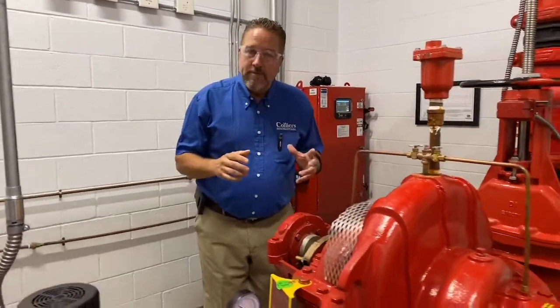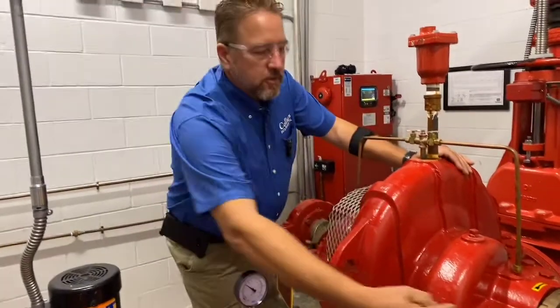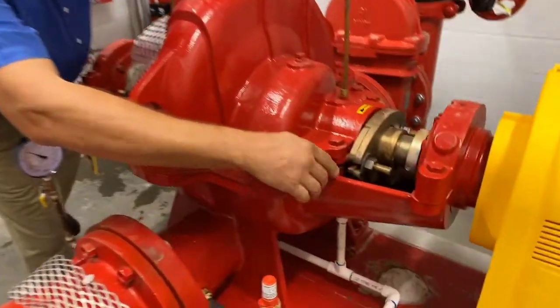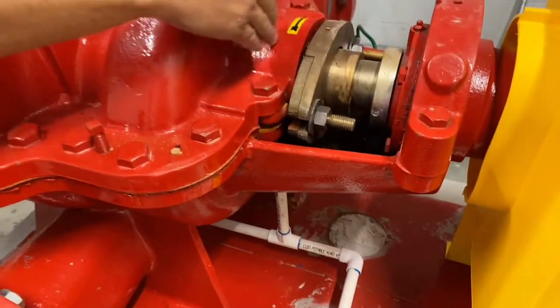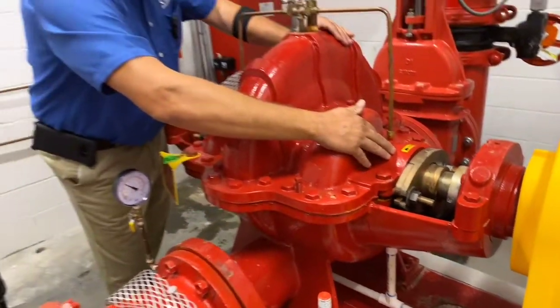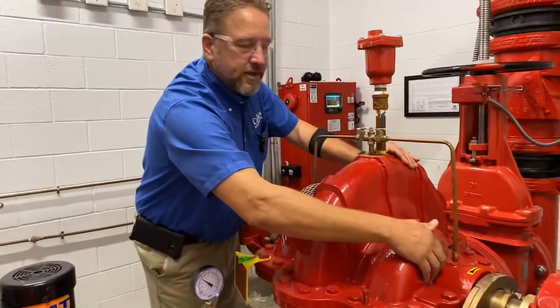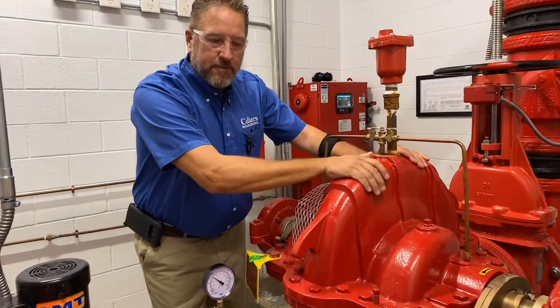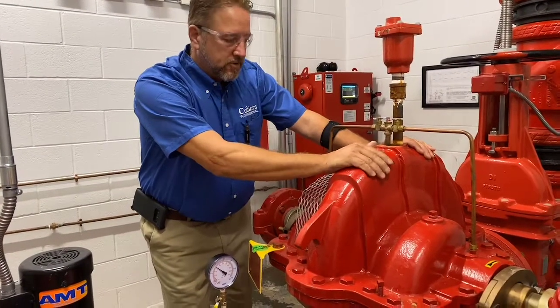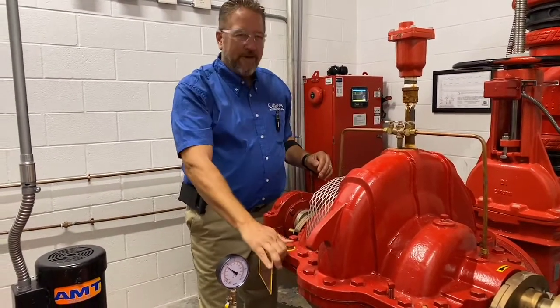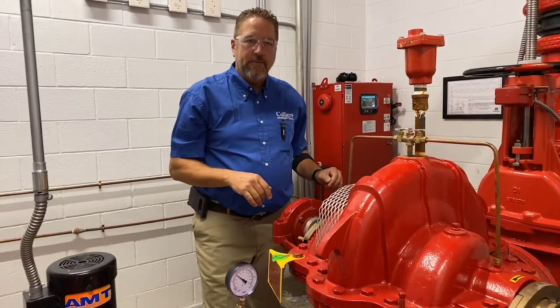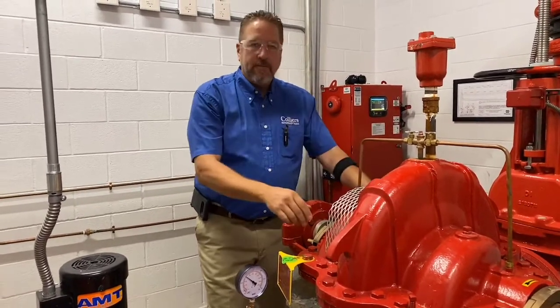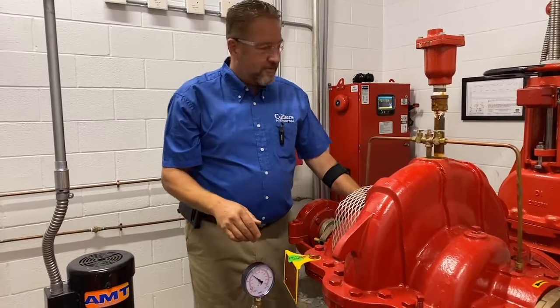Like I said, normally the pump would be running right now. What you're going to look for is to make sure there's a drip in there. What that's doing is water's passing through, keeping your bearings and your packing and everything cool, and your actual pump itself should be cool. Once you get above about 130 degrees, then you need to start worrying about it and get some troubleshooting or maintenance in to give you some assistance with that.